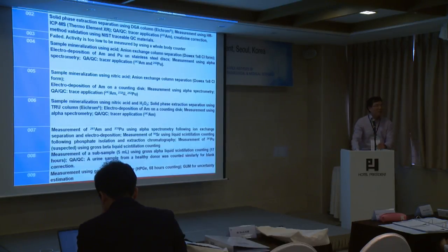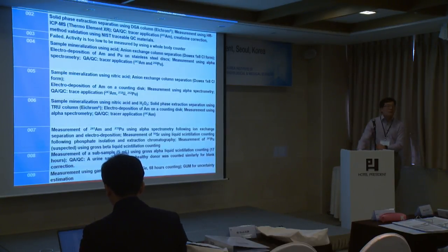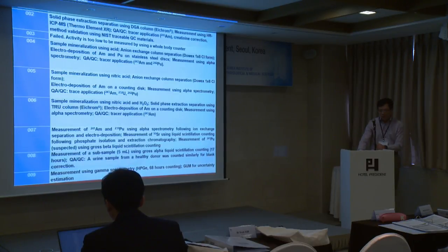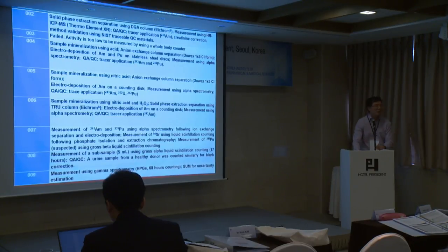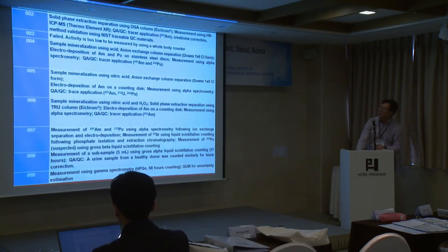Just now, before my presentation, I asked Dr. Yoon, do you have ICP-MS techniques here? In my mind, that is something quite good for bioassay, especially for the long-lived ones. Long-lived ones means the half-life is 100 years or longer. It offers an apparent benefit over radiation counting techniques, because we are measuring the number of atoms rather than the number of radiation emitted from the sample.